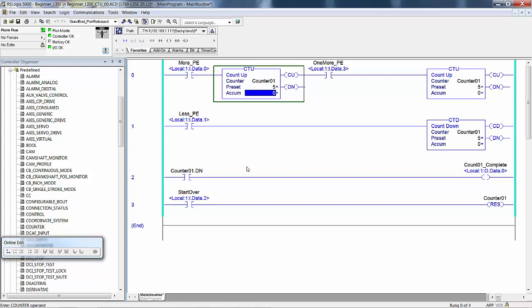When the instruction increments the counter data type one past the maximum, it makes bit 31 on the DINT a 1, which implies a negative value of the previous count of 2,147,483,647. To demonstrate that, I'm going to put that value in there. 2,147,483,647.